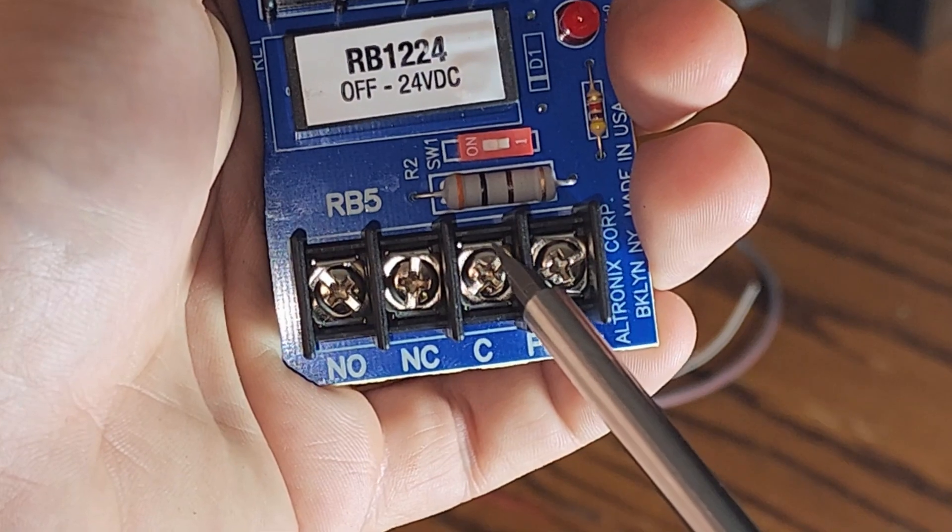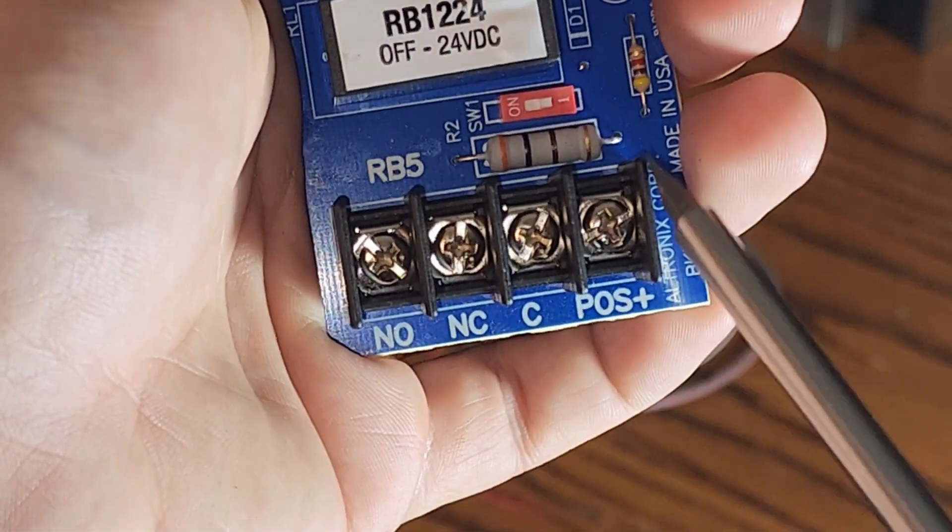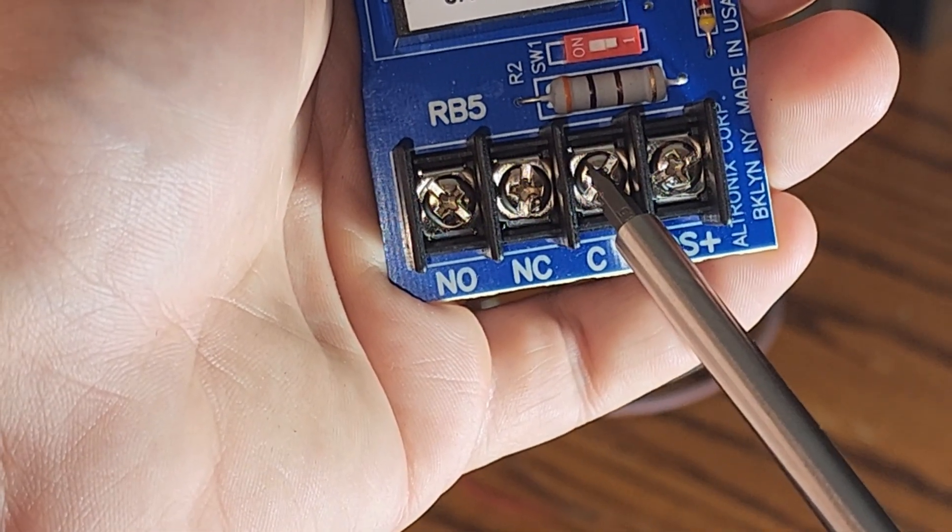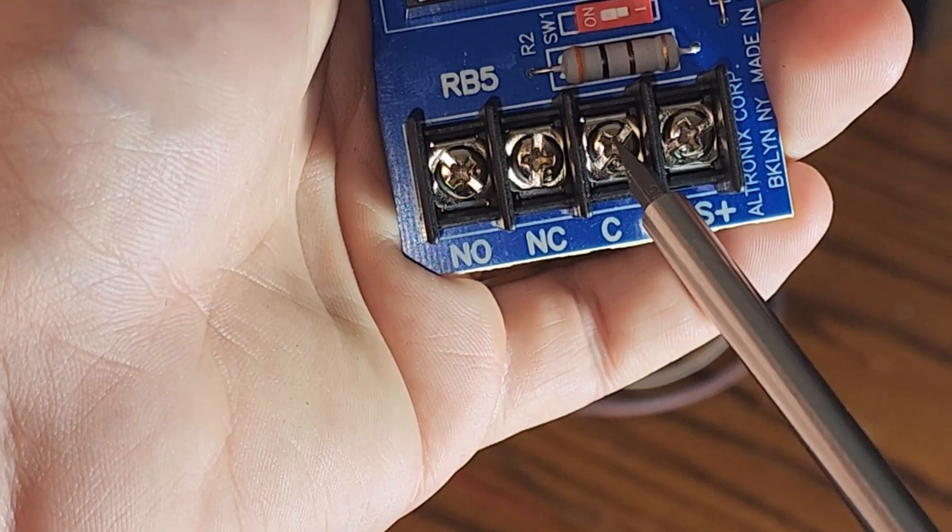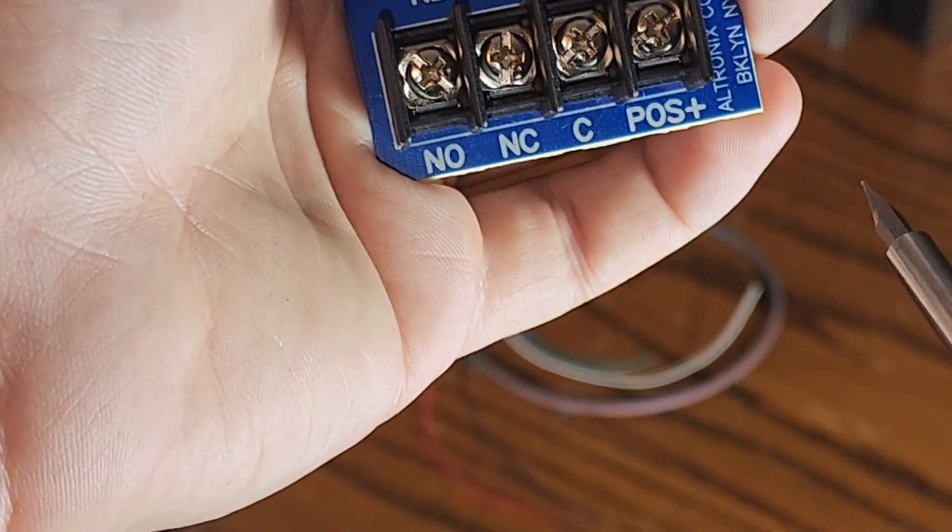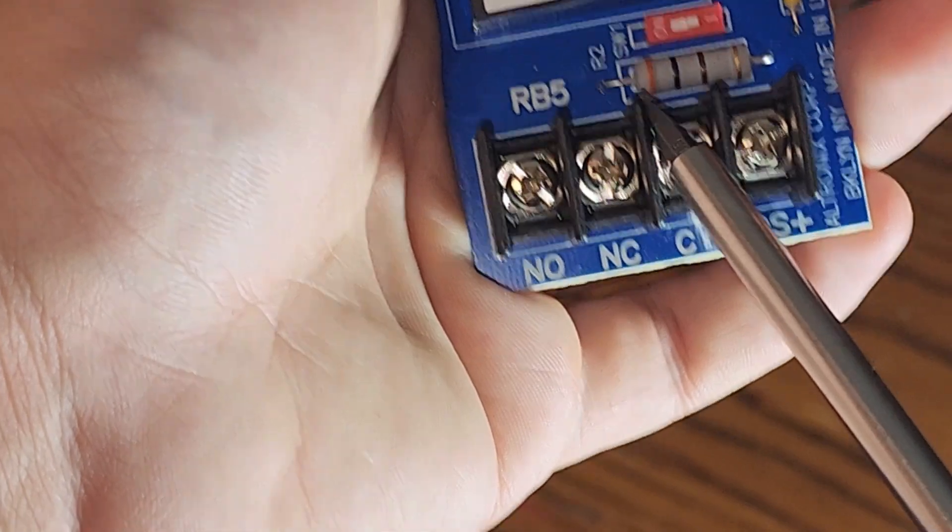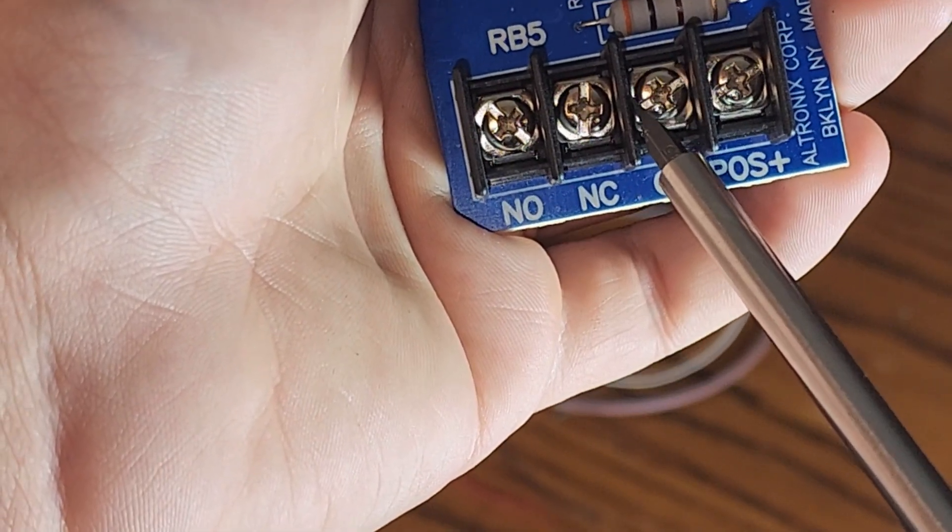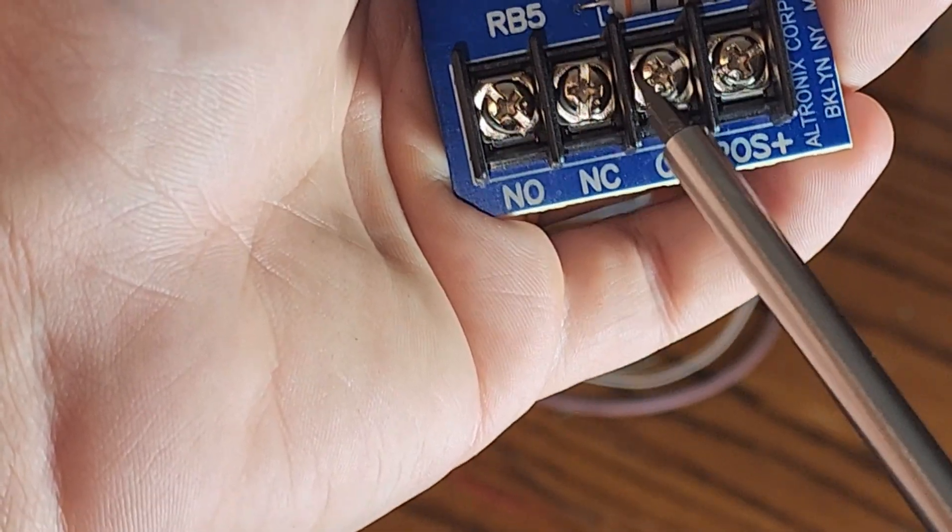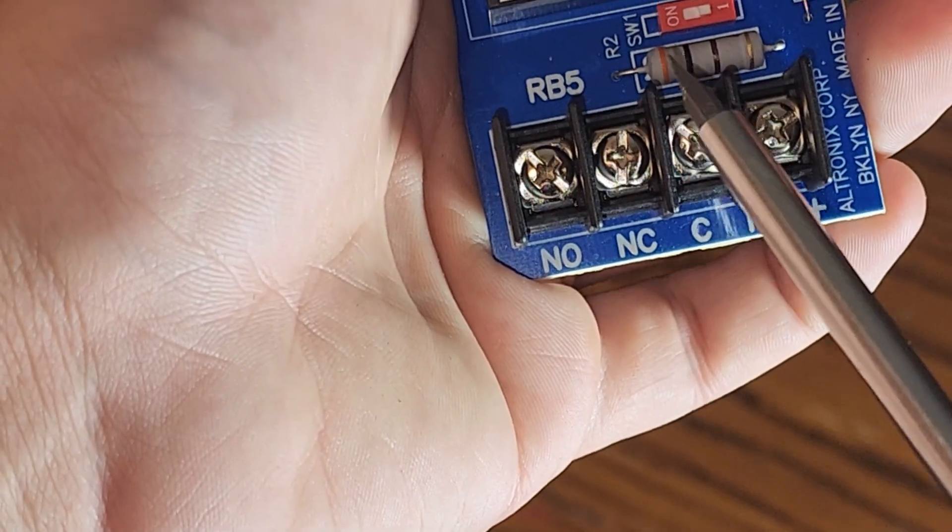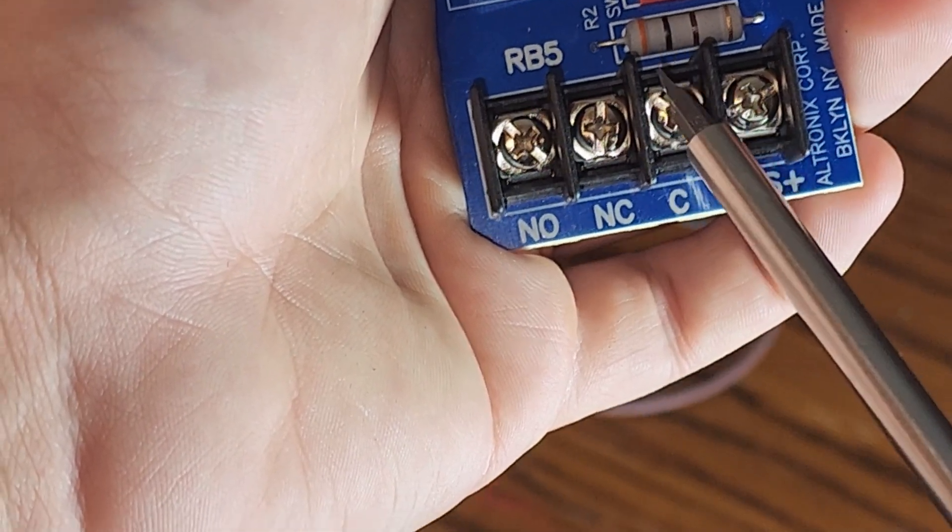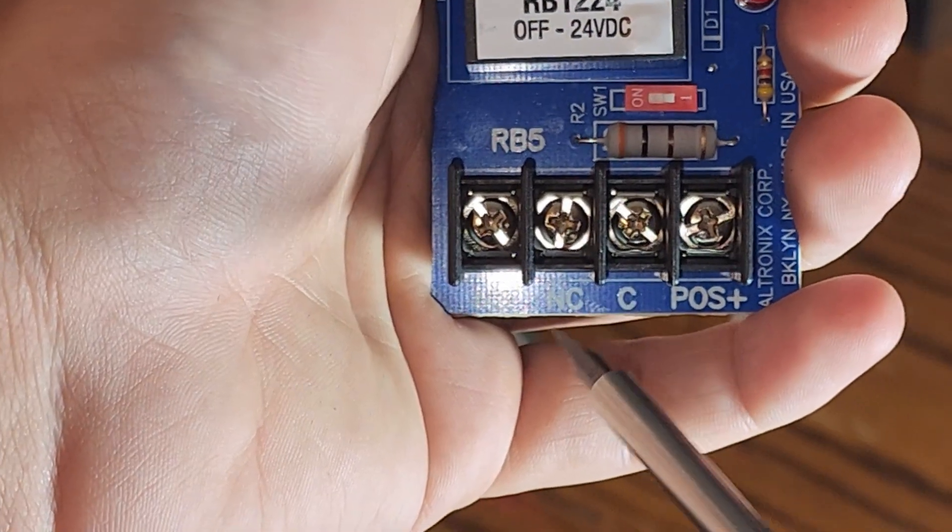I would have either a jumper coming from my positive to this common, or if you're using a separate power supply for your locks, then you will bring a wire in from that, and it will land your positive to your common, or you will land your negative to your common. It doesn't matter which. Generally, negative is safer, but it does not matter in the grand scheme of things.